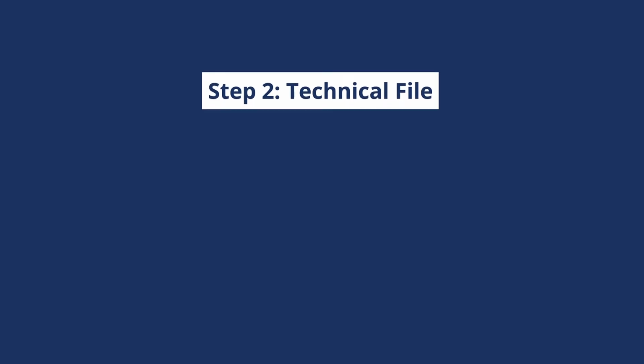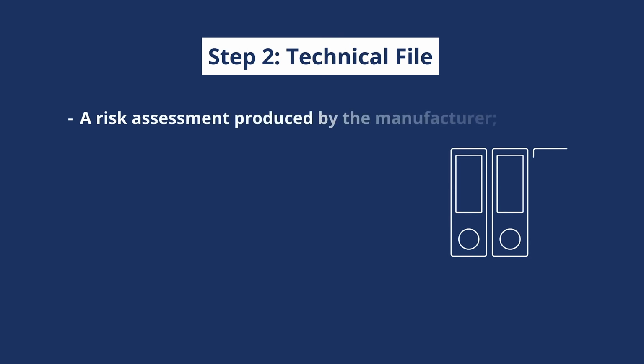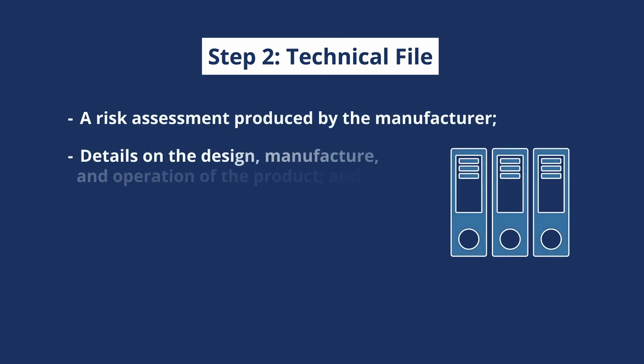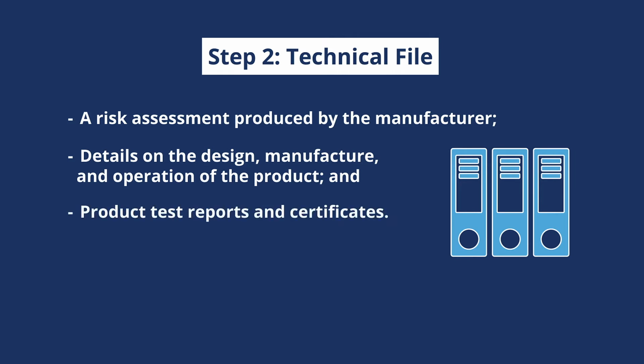Next, manufacturers need to create a technical file to prove that the product meets CE marking requirements. It should include a risk assessment produced by the manufacturer, details on the design, manufacture, and operation of the product, and product test reports and certificates. The technical file must be available for 10 years after the product has been put on the market.